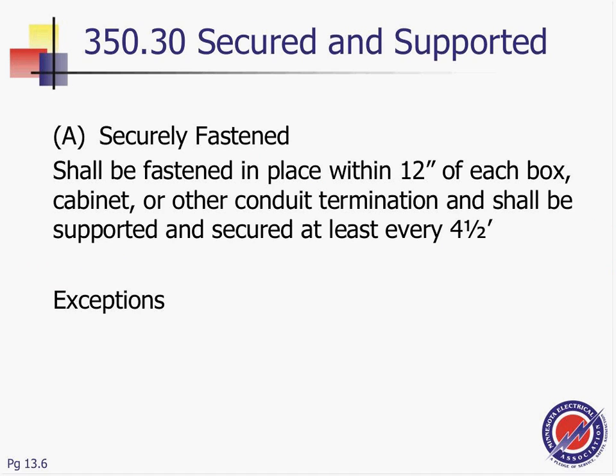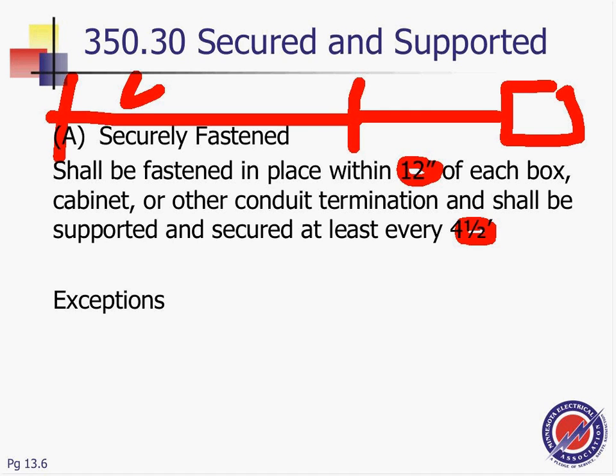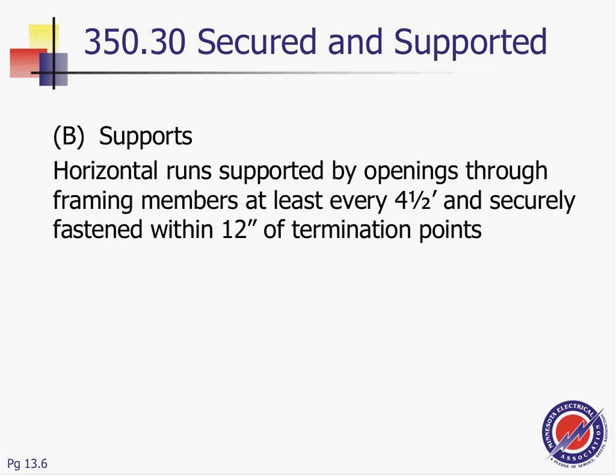Securing is an interesting situation. The same securing, guys, the same secure. You have to secure 12 inches from every box. 4.5 feet in between is my box, is my 12 inches. 4.5 feet in between. 4.5 and a 12. That's the rule. Exceptions, a couple of exceptions. Support. Let's just talk about the support.